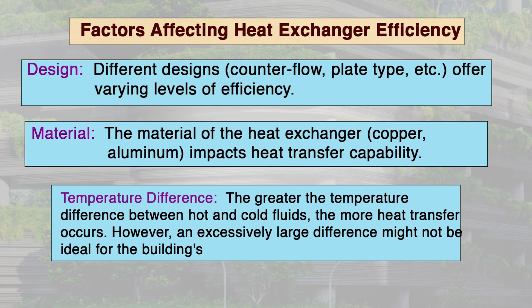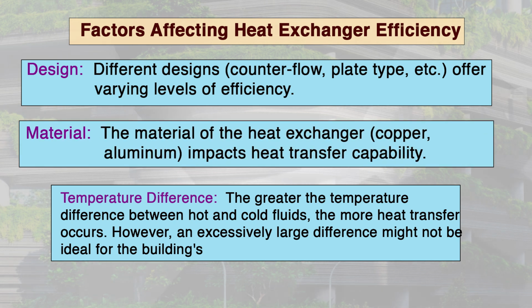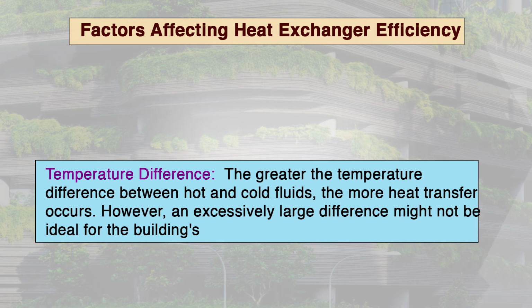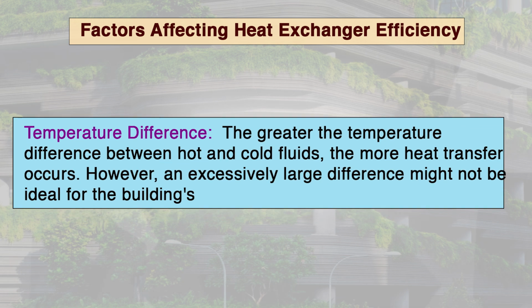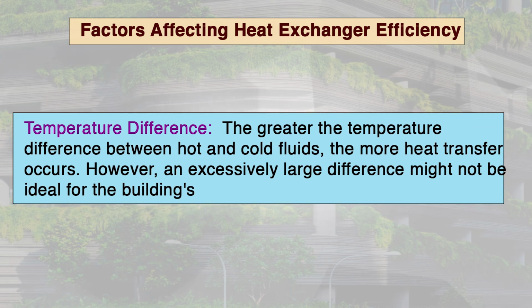Second is material. The material used in the heat exchanger also matters. Copper offers excellent heat conductivity, allowing for more efficient heat transfer. However, aluminum is a lighter and more cost effective option, though with slightly lower conductivity. Choosing the right material depends on factors like budget, application and desired efficiency level. Third is temperature difference. As expected, the greater the temperature difference between the hot and cold fluids, the more heat the exchanger can transfer.